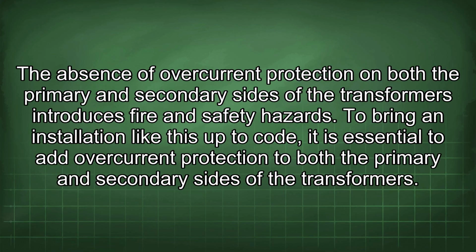The absence of overcurrent protection on both the primary and secondary sides of the transformers introduces fire and safety hazards. To bring an installation like this up to code, it is essential to add overcurrent protection to both the primary and secondary sides of the transformers.